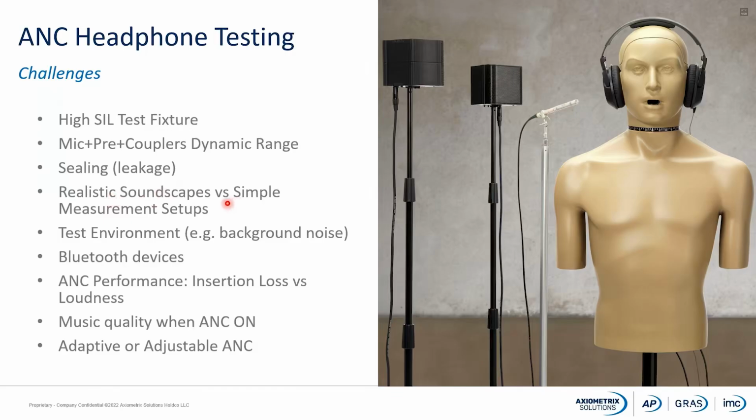Realistic soundscapes versus simple reference signals. As I mentioned before, you can use a realistic signal such as the noise from a coffee shop or traffic noise, or we can use a very simple reference signal such as pink noise. It could be that some devices will perform in a very different way if we are using a realistic soundscape versus a simple signal like pink noise. So this is something that we should look into.